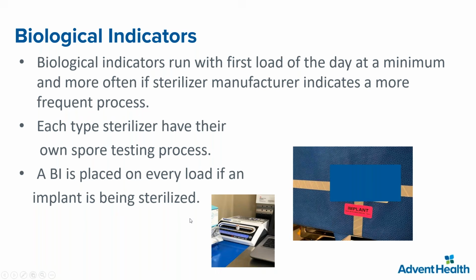The spore goes in a little package. Once the process finishes, and they have passed the strips, the chemical indicators, the process indicator, which is the strip, then we have to see the biological indicators. The three of them need to be in accordance. These work together in order to validate that the load is ready to use in humans. That spore is going to be incubated for 1 hour, and after the hour, if all the process is complete, we are fine. We have the green light to release that tray to be used in humans.